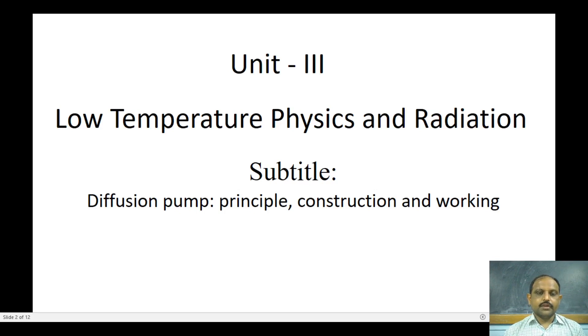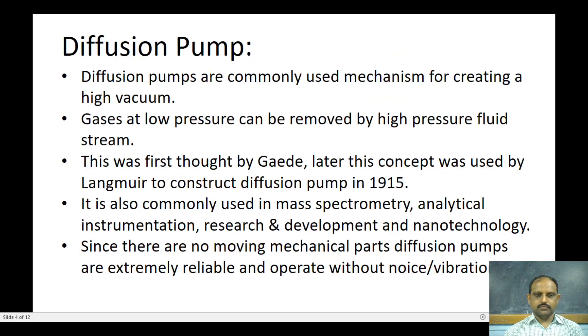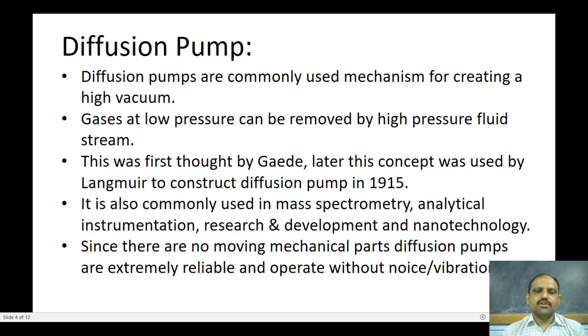In this session, I am going to discuss the diffusion pump. Diffusion pumps are a commonly used mechanism for creating high vacuum. The main principle used in the diffusion pump is that gases at low pressure can be removed by high pressure fluid streams.